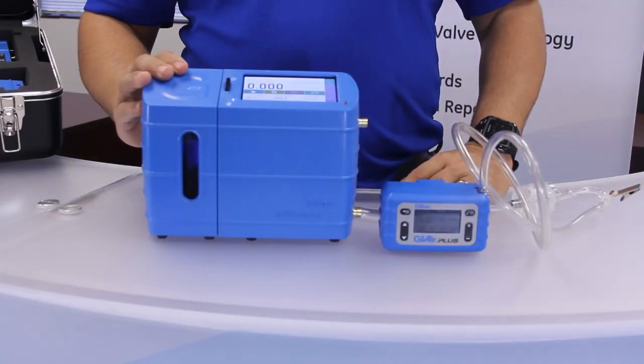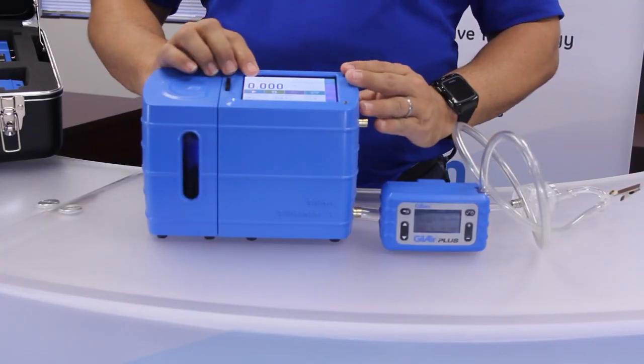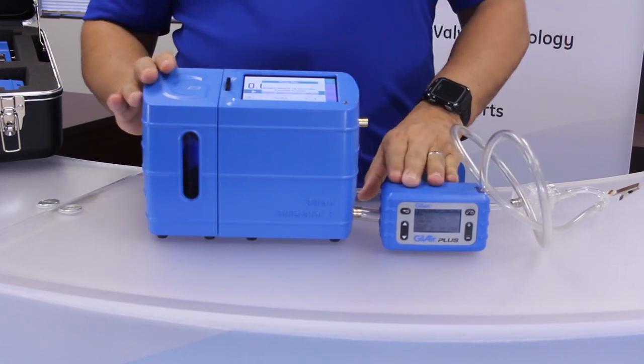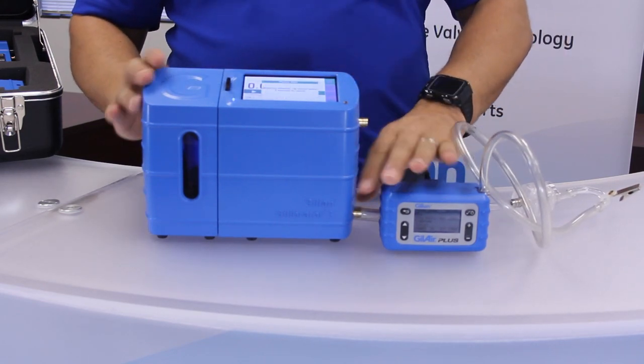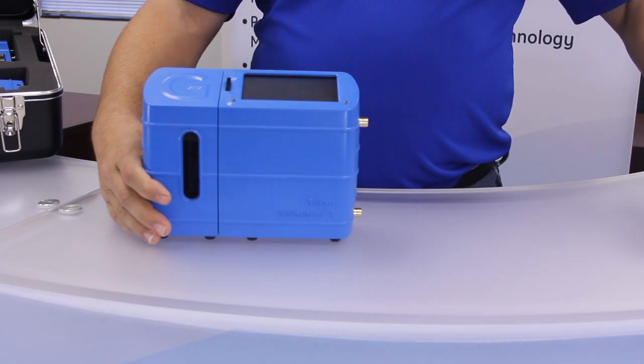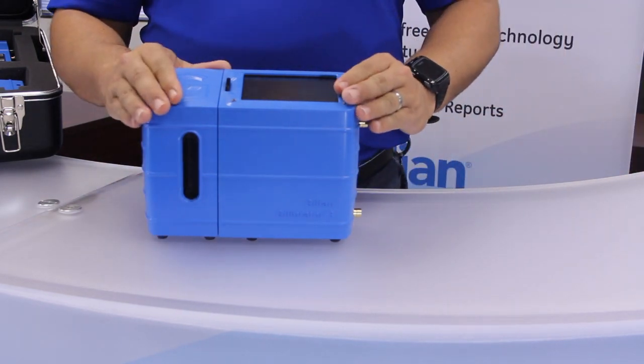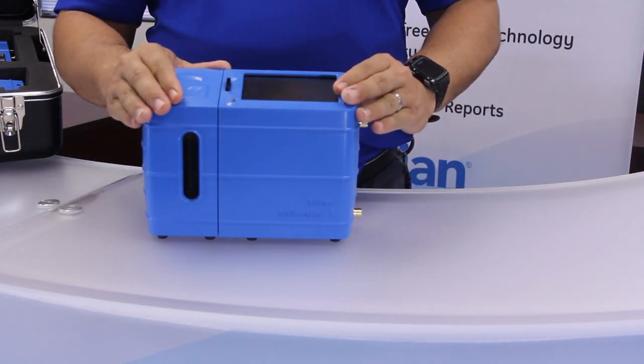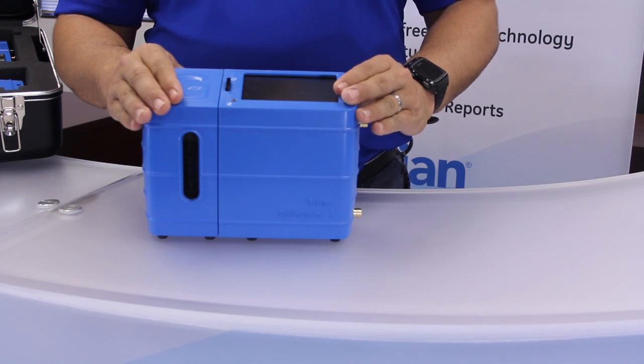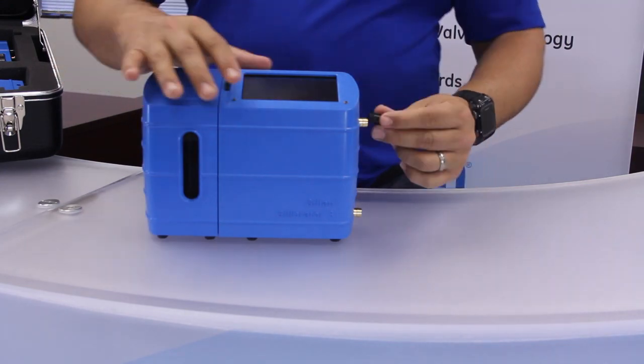For short-term storage, turn off the control unit. If the sample source is still attached, turn it off as well and disconnect it from the base. Any attached output devices, if applicable, should also be disconnected. If the unit is not being used daily, remove the sampling source connection from the fittings. Place the black caps on both the inlet and outlet fittings while not in use.